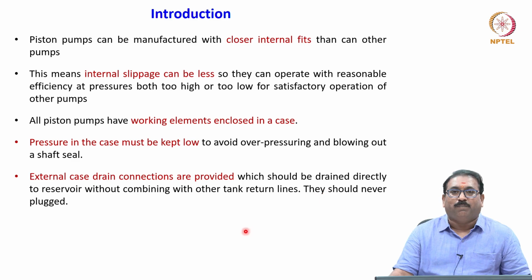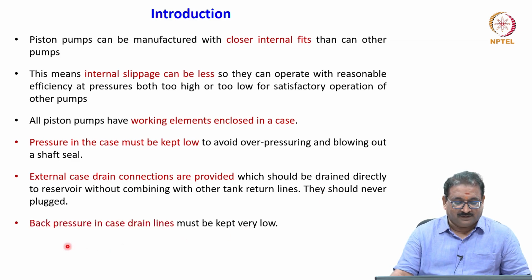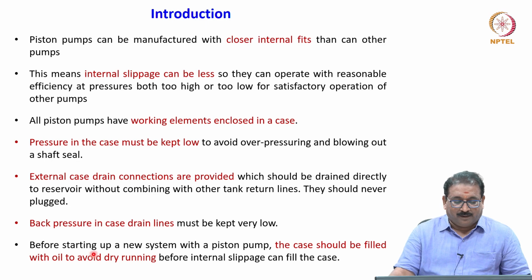They should never be plugged. Back pressure in the case drain lines must be kept very low. Before starting up a new system with a piston pump, the case should be filled with oil to avoid dry running before internal slippage can fill the case.